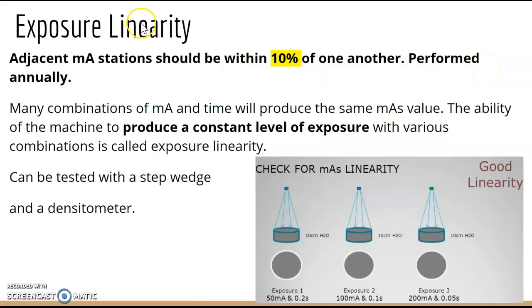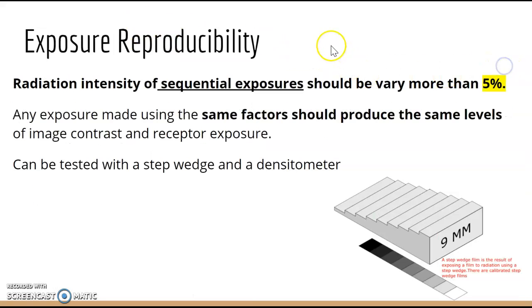Linearity tolerance is 10%. Reproducibility means radiation intensity of sequential exposures should not vary more than 5%. Any exposure made using the same technical factors should produce the same levels of image contrast and receptor exposure.